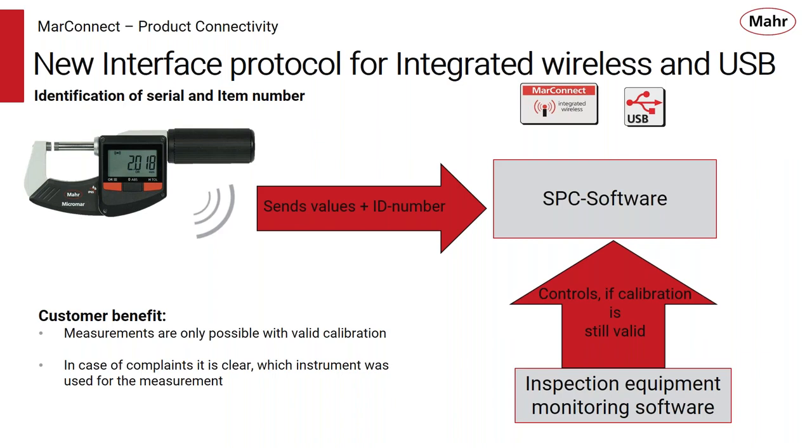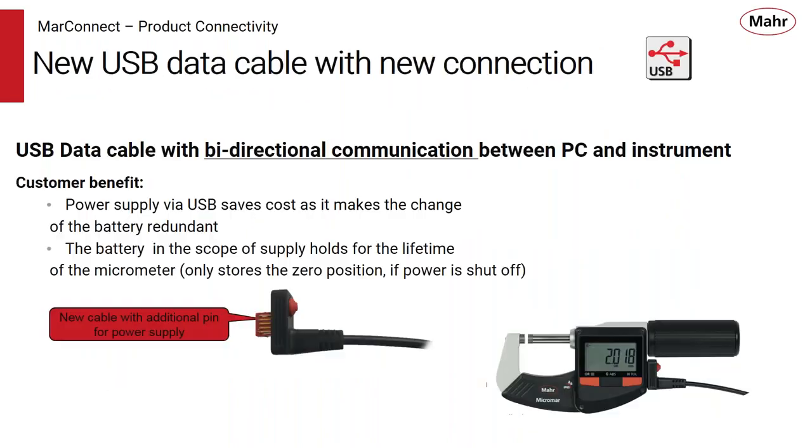Since the gauge number is there, that now can be traced to when the last time it was calibrated or the last time it was serviced. And now you're filling in that whole loop between data collection, knowing when it was done, and knowing which instrument did it. All towards the world of better documentation for your measurements.